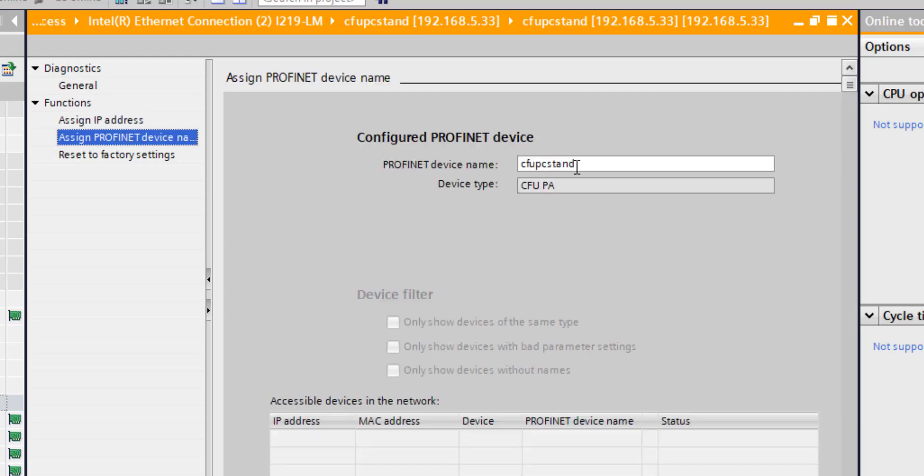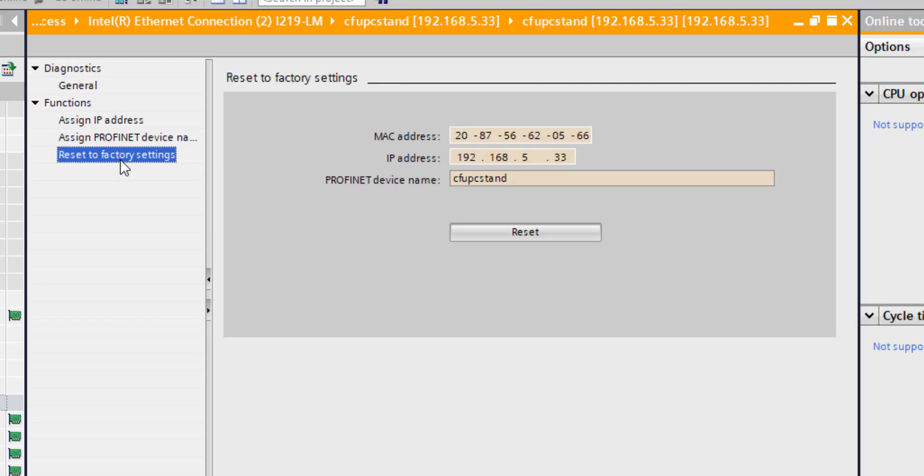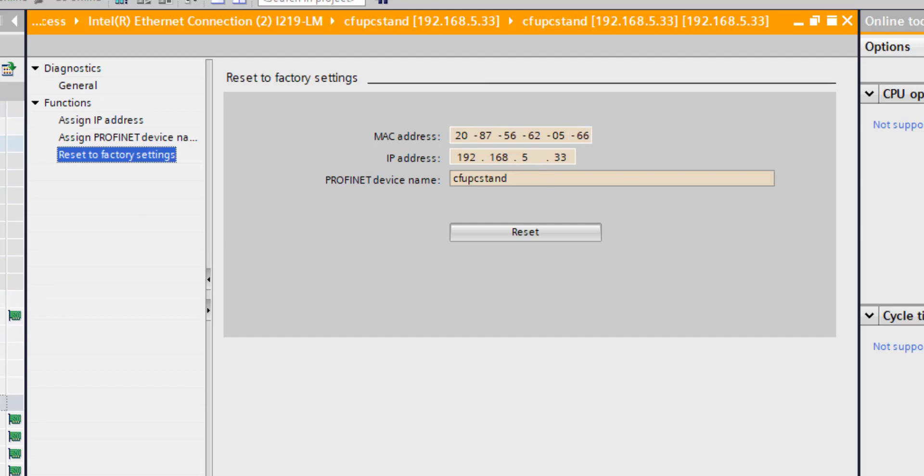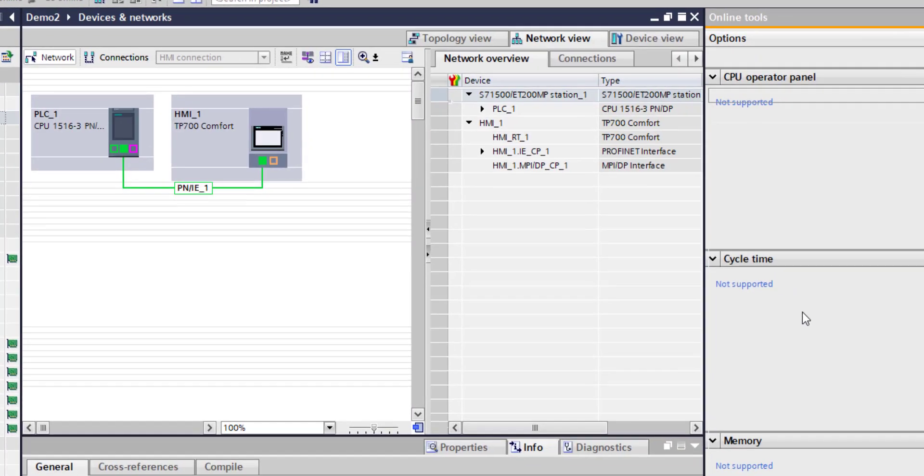If I go to online diagnostics, you'll see under here Functions I can assign its address, I can assign it a name, and I can reset to factory defaults. Once this is in data exchange, I won't be able to do this. At the moment it's not connected and not talking, so I'll be able to do it, but I don't want to change it. I'm leaving it at those addresses. I'll go back to my devices.